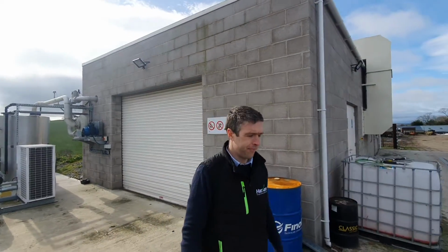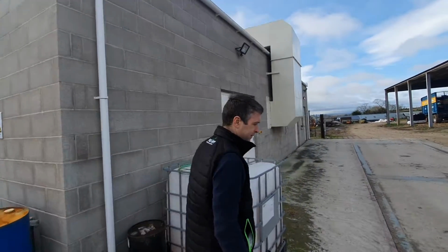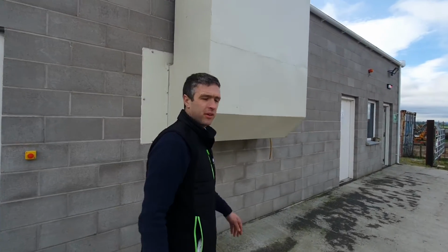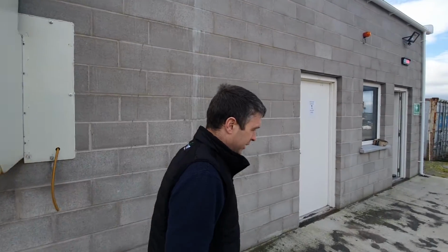We won't be able to talk in there, but you can hear. Yeah, I'm hearing a lot of noise. So I guess that's the engine inside there. Yeah. So the gas is converted into driving an engine to make electricity. Is that the principle? Yes, the biogas is basically the same as a natural gas engine. Your energy value is about half of what natural gas is, if you're at 50-55% CH4. So it's basically a derated natural gas engine.